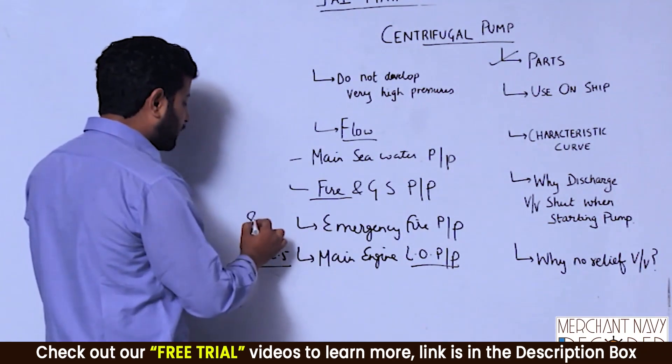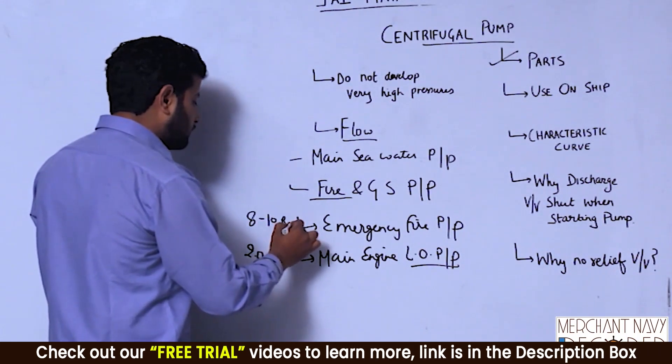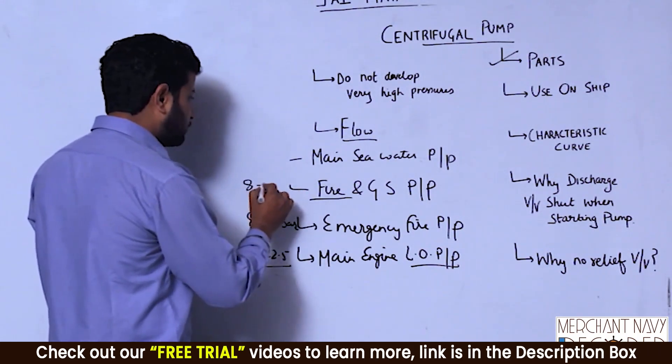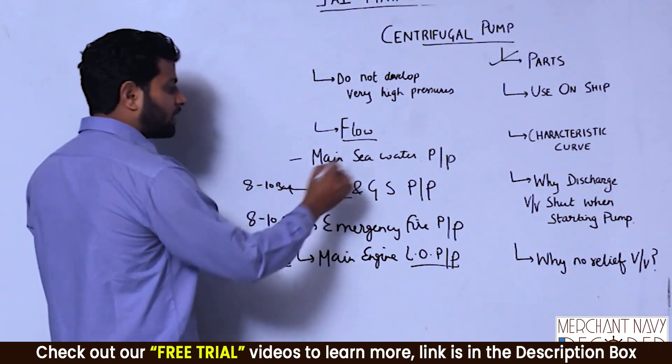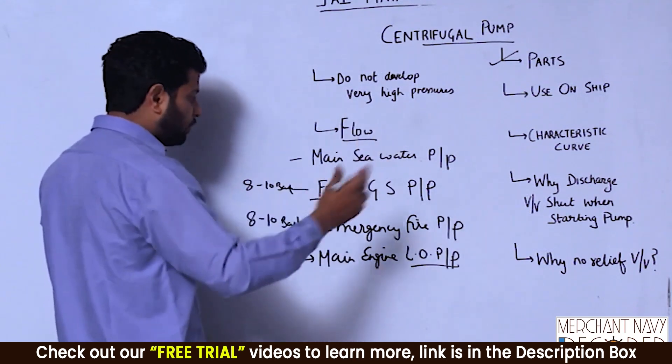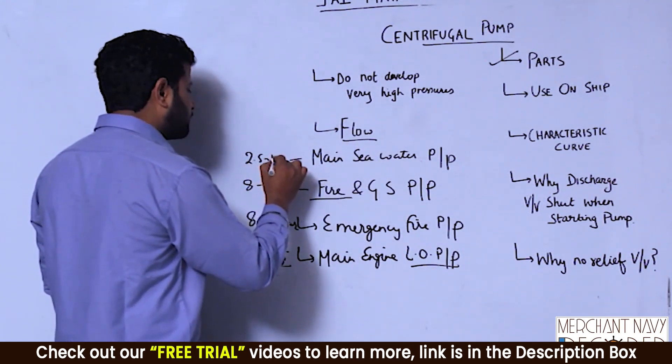Emergency fire pump can go up to 8 to 10 bars. Same goes for fire and GS pump, 8 to 10 bars. In main sea water, we have a lot of flow but pressure not more than 2.5 to 3 bars.